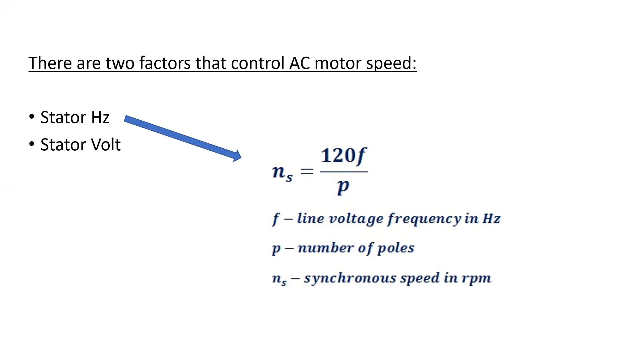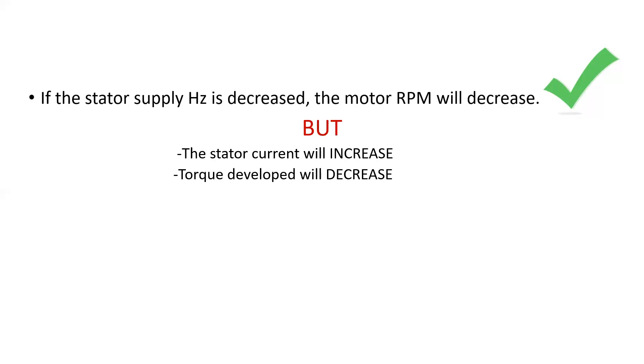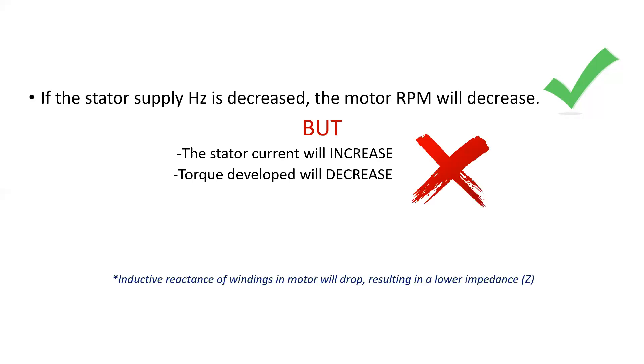The stator voltage will also lower the motor speed if it is driving a load. But there's a problem. If the stator supply hertz is decreased, the motor RPM will decrease. However, the stator current will increase and the torque developed will decrease. The reason for this is that the inductive reactance of the windings in the motor will drop because of the supply frequency going down. This will result in a lower overall impedance, and due to Ohm's law, more current will be drawn.